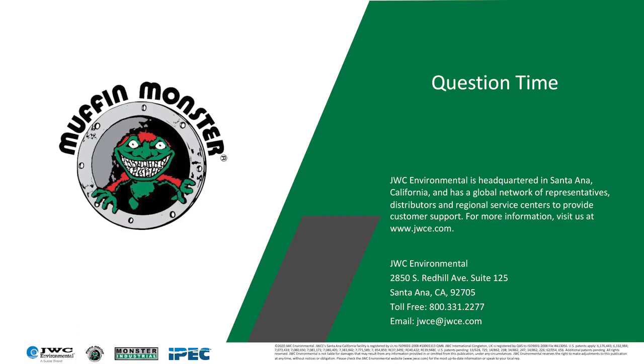So the last question, Jesus, is can high pressure wash water required by a fine screen system be supplied by processed water instead of municipal potable water? Absolutely. The answer is yes, and in 95% of the cases that's the case. We just have to understand the nature of the process water, and we'll always tend to provide additional screening for that water. We'll provide screens for the incoming wash water, typically a Y strainer type, maybe with 80 mesh or 70 mesh, so that we don't clog the nozzles in the cleaning system. But yes, absolutely, we can use processed water.